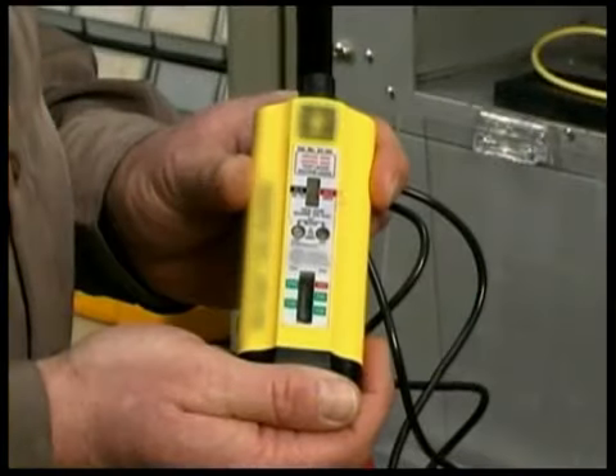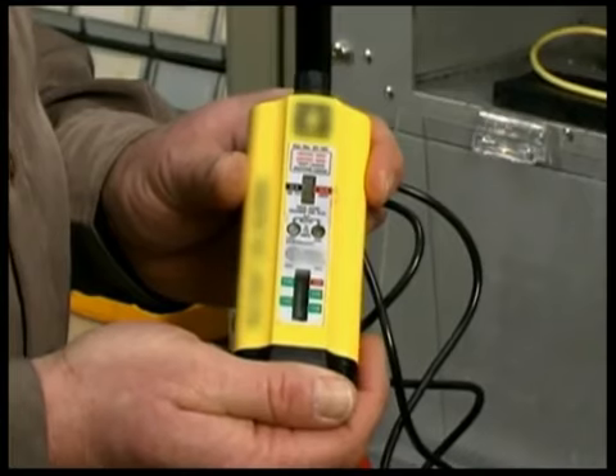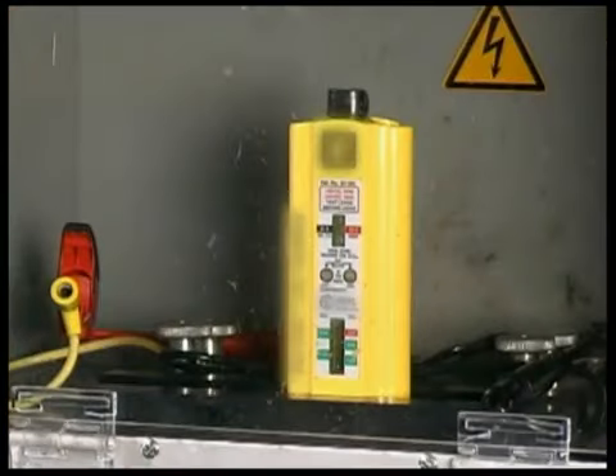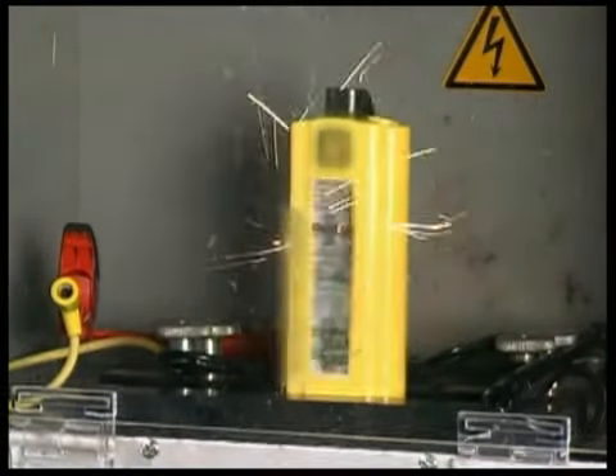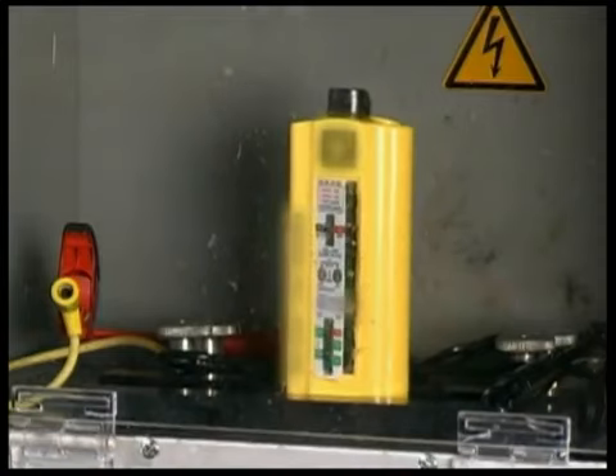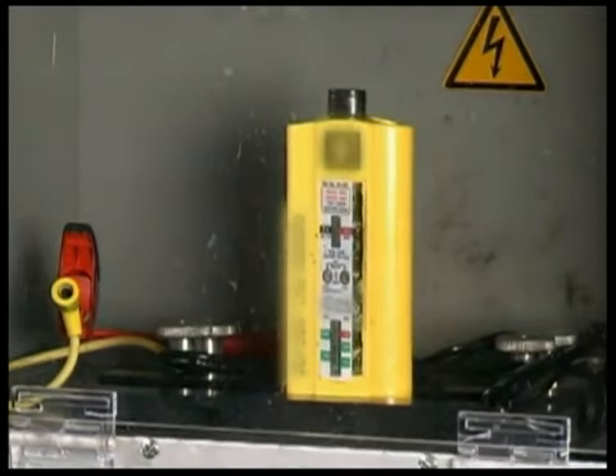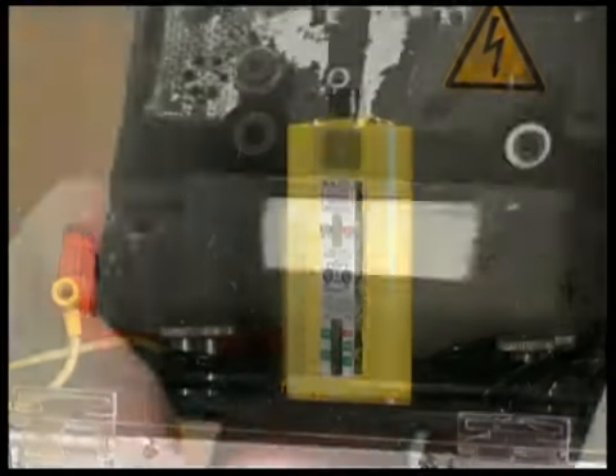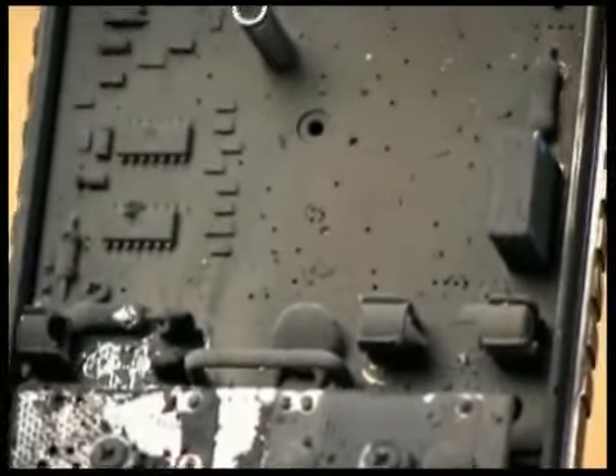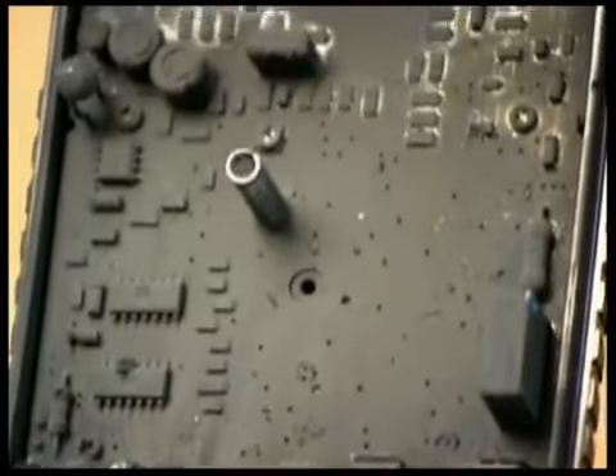Here's what can happen when a meter marked Cat 2 is used in a Cat 3 environment. In a real Cat 3 or Cat 4 environment, the arc would have been fueled by thousands of amps. The resulting arc flash could cause serious damage. In addition to transient protection, a meter should be able to withstand accidental overloads associated with the various functions of the meter.